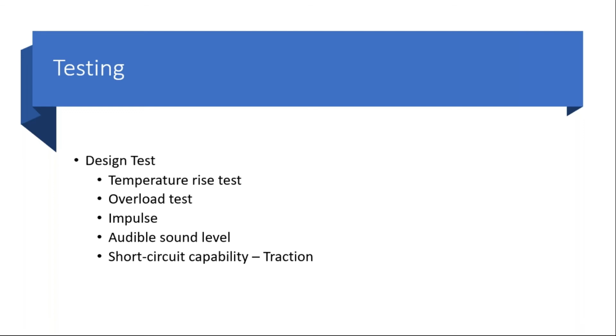And short circuit capability test is very common for traction transformers. We have seen every customer is looking for the first transformer to be tested for short circuit of its design. And sometimes they ask us to have it short circuit tested, but sometimes there is a contractor in between or an engineering firm who has a contract for the full substation. They would take it. So either way, in fact, if you look at our short circuit test transformer data, most of them are from traction duty.